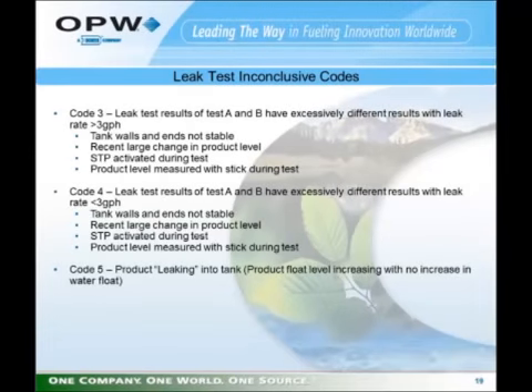When the EECO conducts a static leak test, it actually conducts 2 tests, Test A and Test B, and compares the results of those 2 tests. If you receive an inconclusive code 3, it means that the leak test results between Test A and Test B are excessively different and indicate a leak rate of greater than 3 gallons per hour. This can be caused by the structure of the tank being unstable, a recent large change in product level, submerged turbine pump activated during the test, or even if someone checked the product level in the tank using a manual stick during the test.